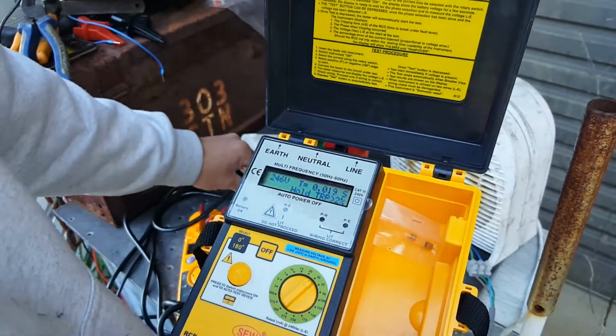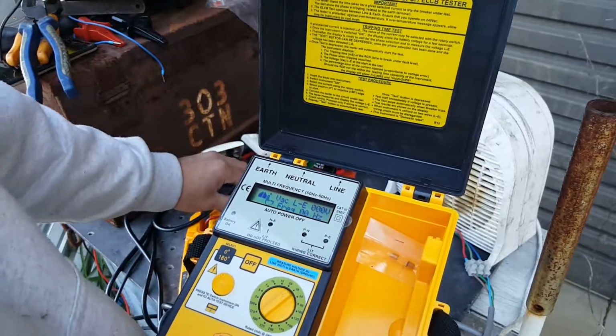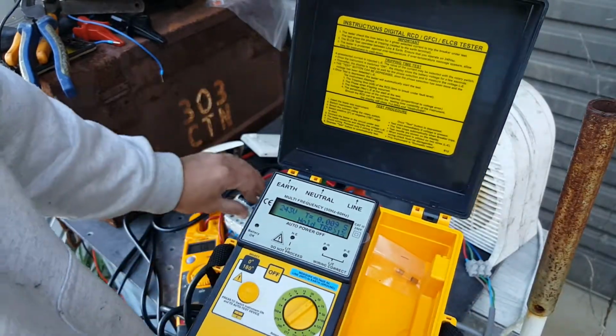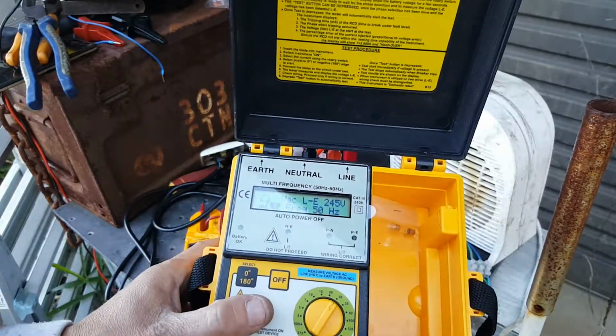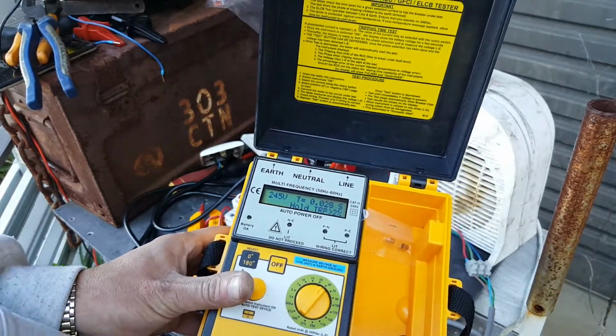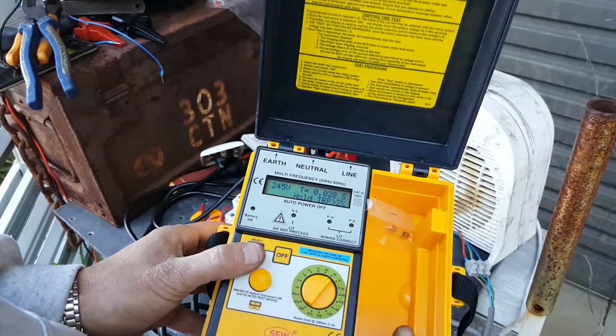So, not impressively quick. The Voltex one actually was better from memory. We'll just check the other 180 direction. Much quicker in the other direction. Okay, the second one. What's this one, this one's a 10mA. So yeah, a little bit slower on that one. Try in the other direction.